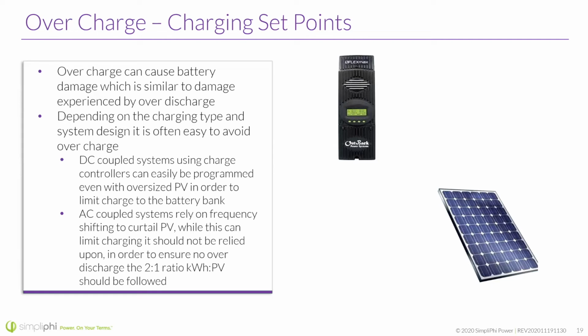DC coupled systems use charge controllers typically, or I would say almost, I can't think of a situation where they really wouldn't. Those can be easily programmed, even with an oversized PV relative to the charge controller. They all have their limits, in order to limit the charge to the battery bank. So, you've got a 3 kilowatt PV array and your battery bank can only handle 1.9. Your charge controller can typically be that threshold point. Super easy to program. Say, I don't want it to ever charge more than this. And that'll work almost every time, as long as the programming doesn't get scrubbed for any reason, which is always good to check after a firmware update.